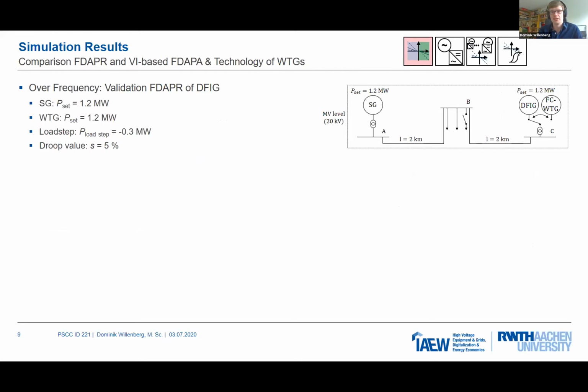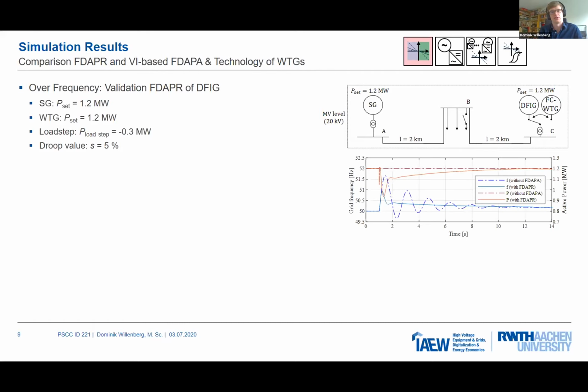What we see here on the right side is the topology which is used. The synchronous generator and the wind turbine generators each have a set point in active power feed-in of 1.2 megawatts, and a load step of minus 0.3 megawatts is performed. The droop value, in that case the default value, is set to 5%.